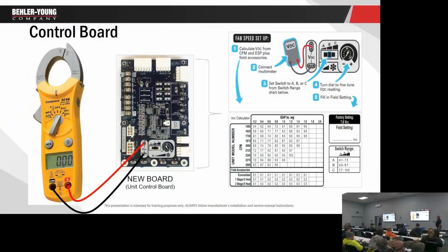Okay. Then do you add the curb adapter? Well, if I had it, I would add the curb adapter. So if I had 0.9 plus 0.1 for the economizer, in that example, I had 0.8 for my curb adapter, I got 1.8 inches of static. Now, this was a big, big unit, but I'm almost at 2 inches of static right off the bat, which there's no system, there's no blower we sell that's going to handle 2 inches of static.